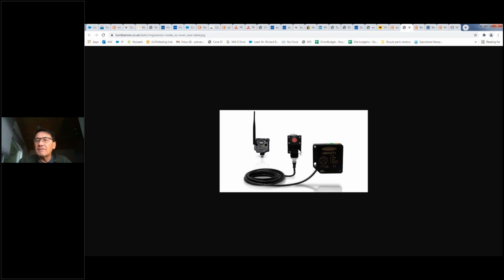This is going back to an RFI transmitter. This RFI transmitter basically will take the place of cable running back over hill and dale to a receiver that can then be wired directly into your PLC or whatever other programmable device you're using to sense the signals from the vibration sensor. And you will get the vibration data plus status on the pre-warning and fault levels that you've programmed into the little sensor in the field. A very nice setup, and we're talking probably less than $600 for the whole thing.